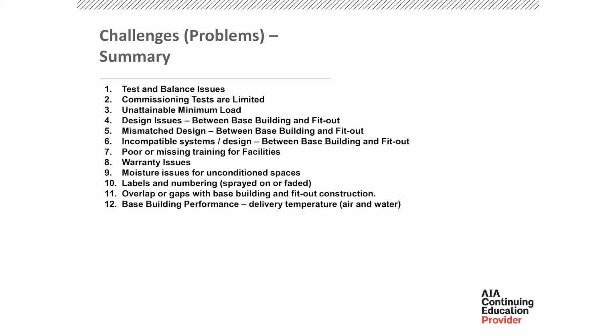So here are some problems with core and shell. Test and balancing issues. The commissioning test is limited. Sometimes you won't be able to test a system because you don't have the full system erected on the site. So, unattainable minimum load. If it's operating at minimum capacity, you might never be able to meet your minimum load at all. Mismatched design between the base building and the fit out, because each system is built by a separate team sometimes, and there's no communication between the two. Incompatible systems between base building and fit out. A lot of times you'll have a base building automation system that won't connect to the fit out automation system, so you have two running side by side.